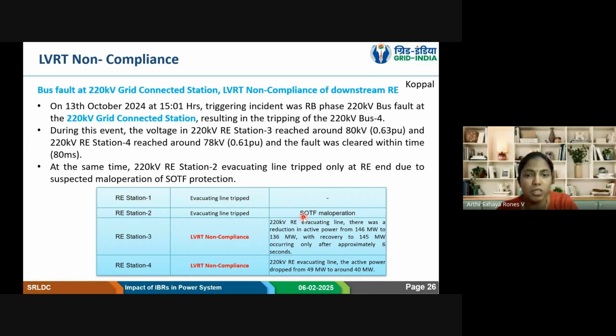Usually if it is zone 3, then it is assumed that the fault is beyond, in some other line. But if the remote end is not picked up, the remote is open, and the line is like idle charge, then obviously the fault is there in the line. So for that kind of protection, for early clearance of the fault, we have this function called SOTF.